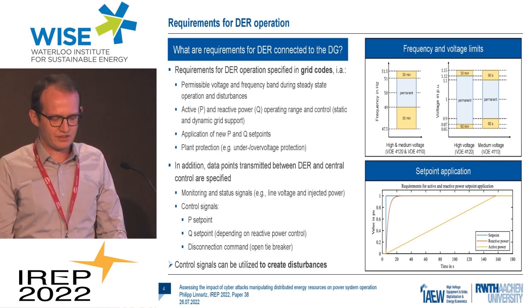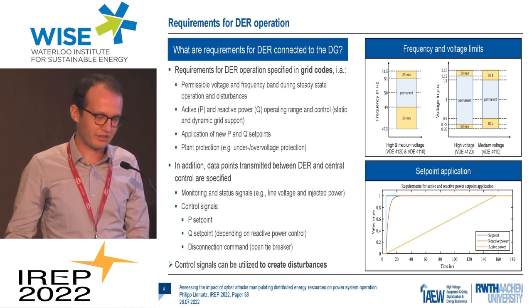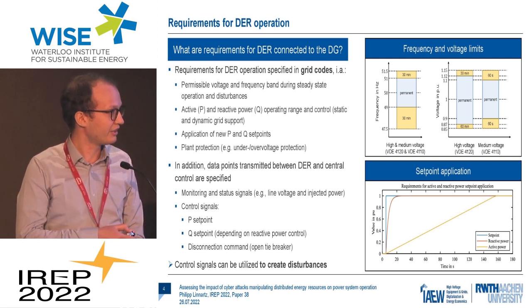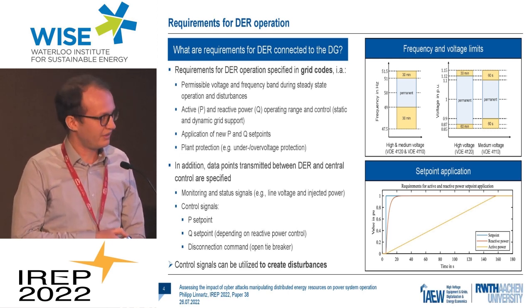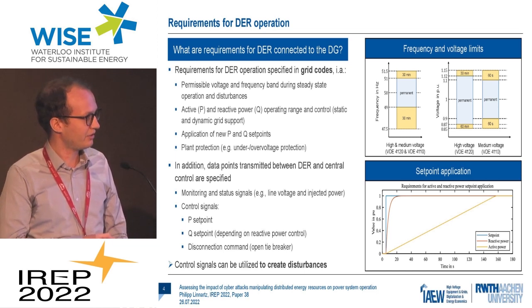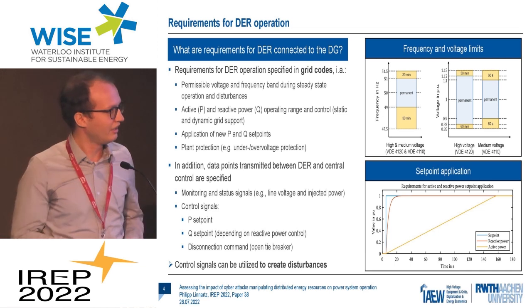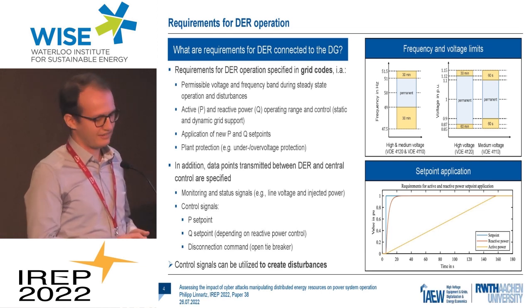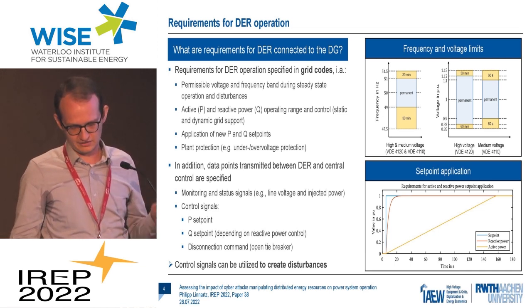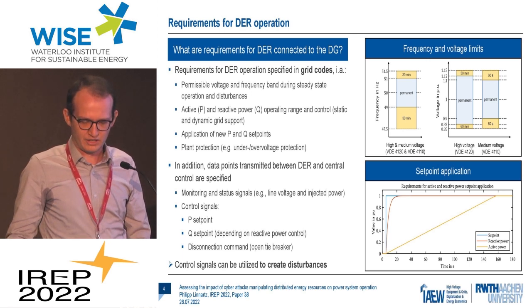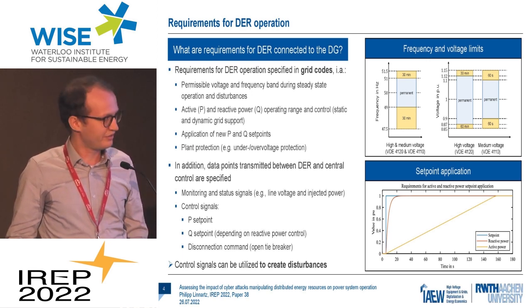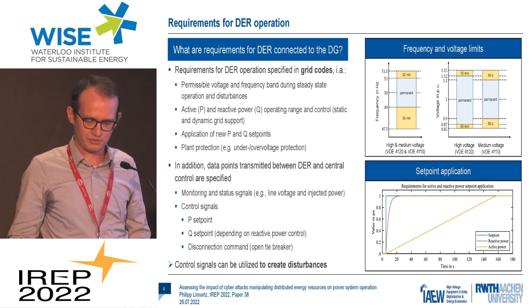They also specify how to apply new active and reactive power set points, as indicated in the figure on the bottom. So if the DER receives a new set point, saying from 0 to 1 per unit of active power injection, then this kind of ramp applies, which limits the slope of the rise. It takes around 150 seconds for the new set point to be reached.